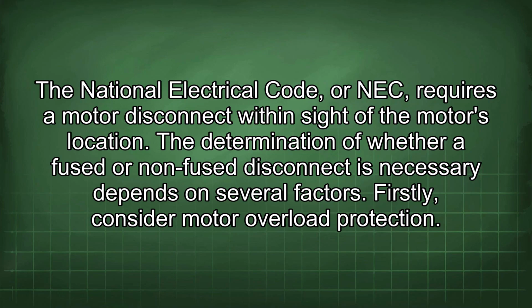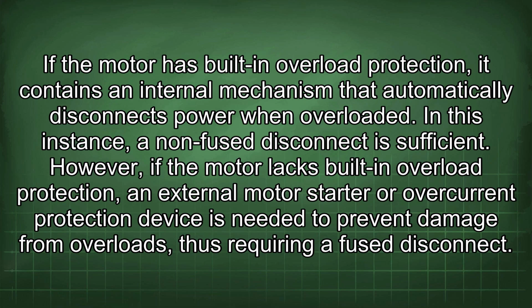The National Electrical Code, or NEC, requires a motor disconnect within sight of the motor's location. The determination of whether a fused or non-fused disconnect is necessary depends on several factors. Firstly, consider motor overload protection. If the motor has built-in overload protection, it contains an internal mechanism that automatically disconnects power when overloaded. In this instance, a non-fused disconnect is sufficient.